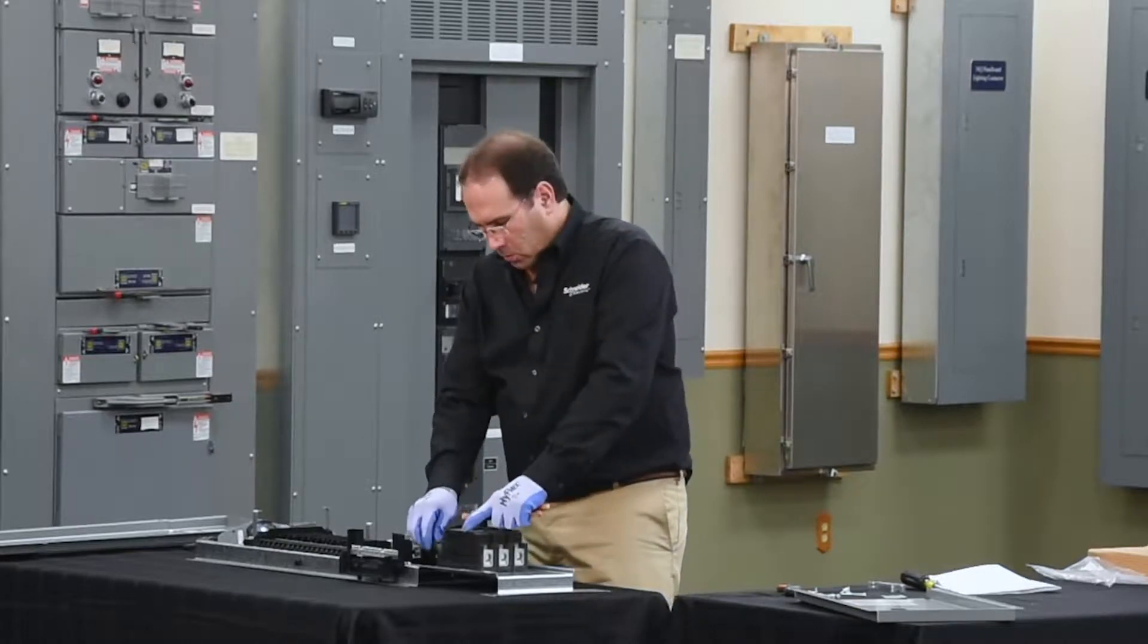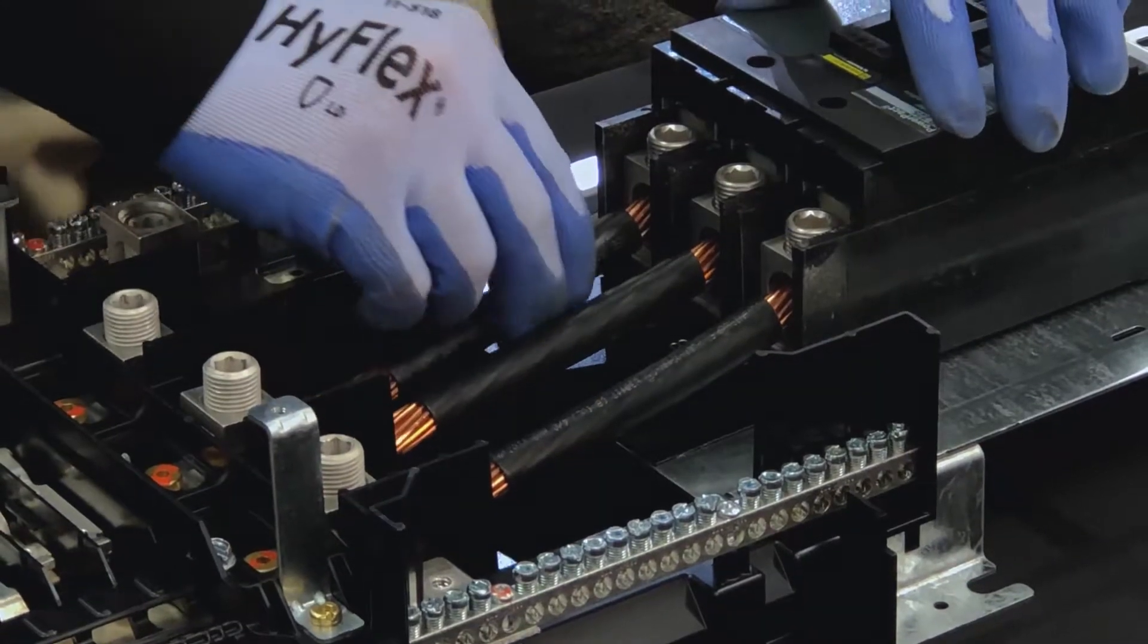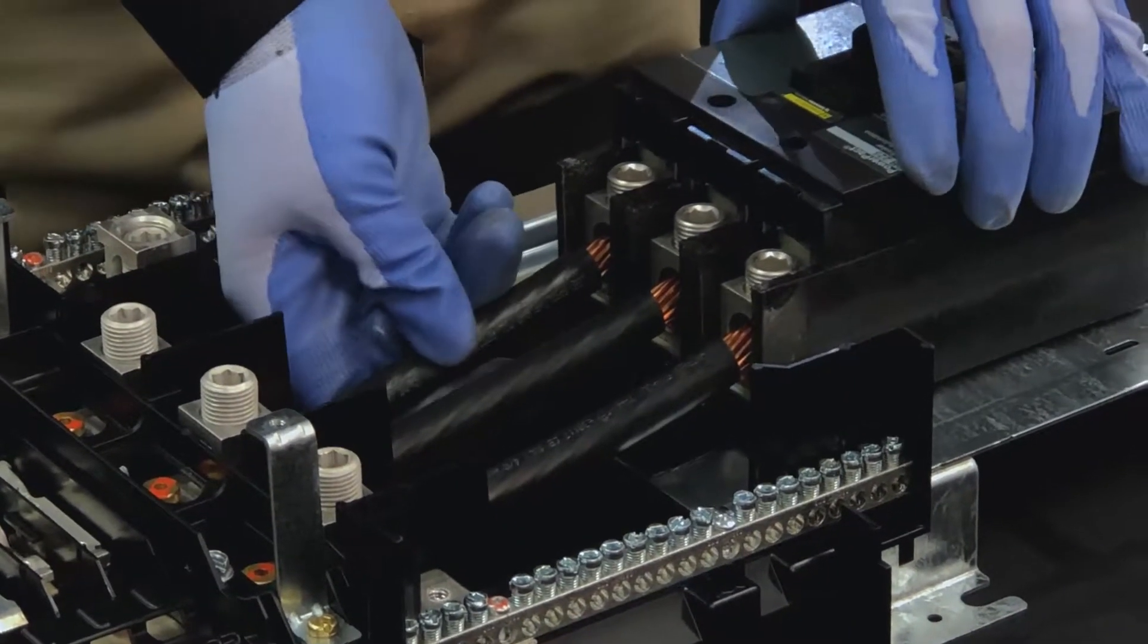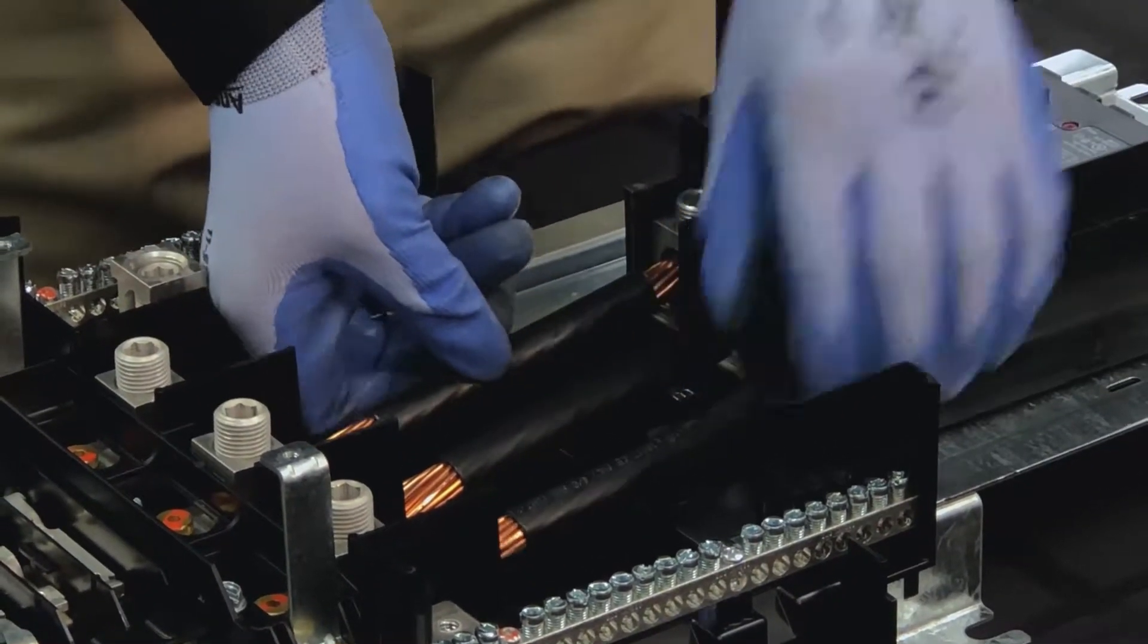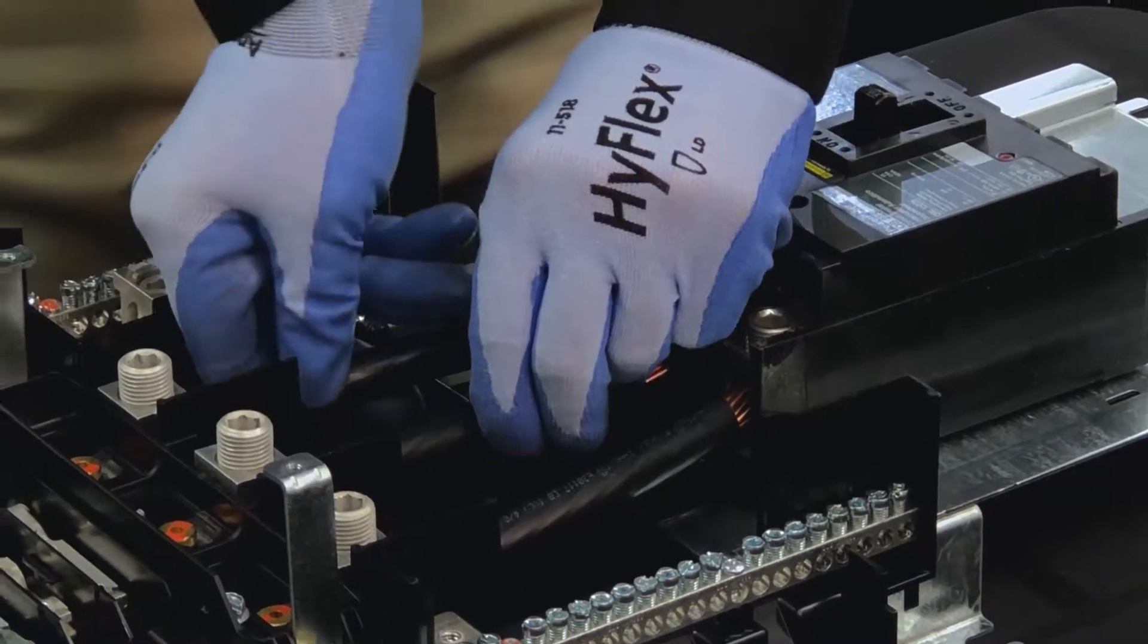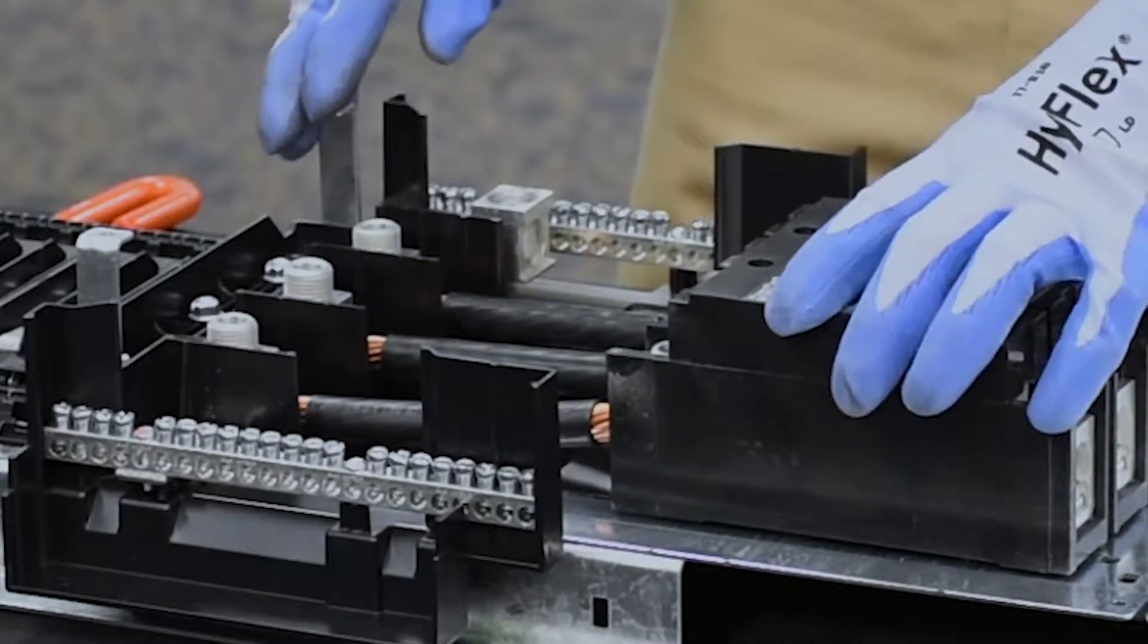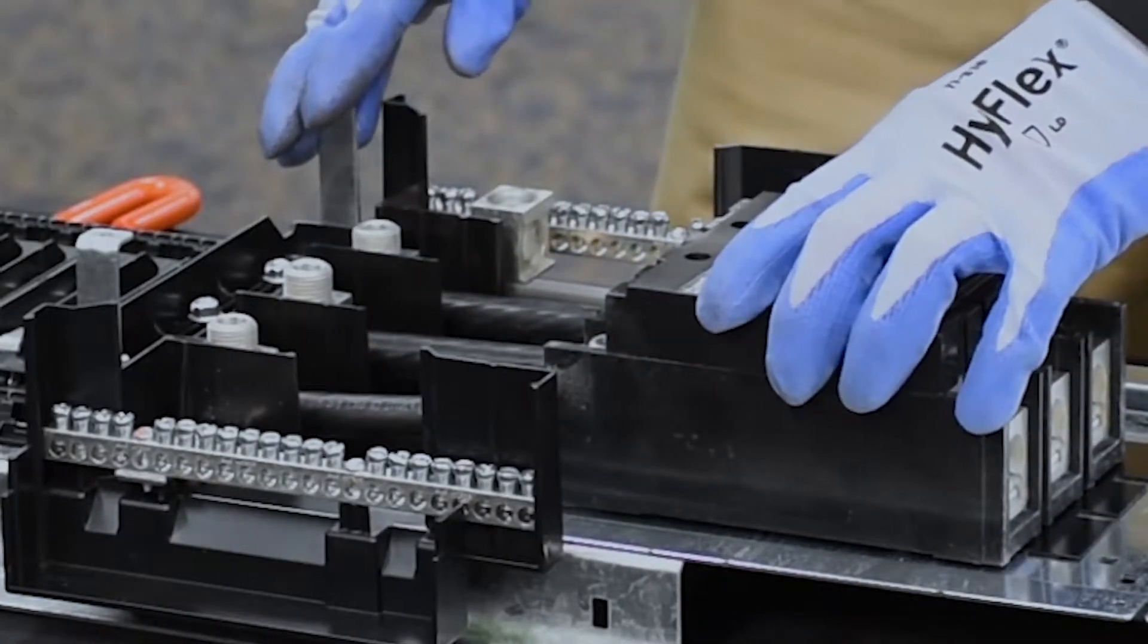To install the cables, you want to leave them loosely sitting inside the lugs of the breaker. Slide the breaker close to the panel board and then slowly move the cables into the lugs of the panel board, and then slide the entire assembly forward.